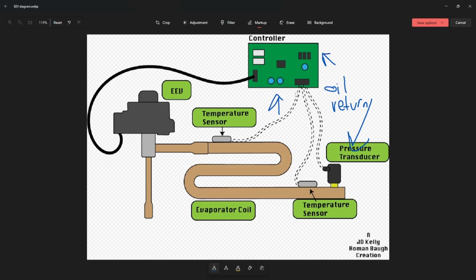Sometimes that'll generate a fault code or an error code. Sometimes it will not. Sometimes it just goes into a step down or a throttle back, where it'll actually try to pick up the suction pressure to keep it above freezing in an effort to avoid that freeze up. It'll do that sometimes in applications where there's low heat load, like on a mild day, or if it's starting to see an airflow restriction, like if your filter's getting clogged. But those are the primary applications you'll see a pressure transducer.